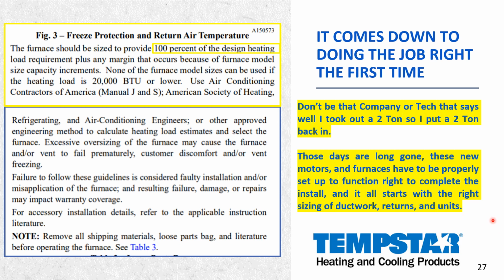Now, ICP looks at this as up to the installer or the contractor that is doing the install to read the install manual and make sure the furnace or air handler or equipment is set up properly in a proper install to be successful or to consider a good install. Everything has to be sized and done exactly right. And this could violate warranties in the future. So make sure the ductwork is set right and your CFMs are set right.